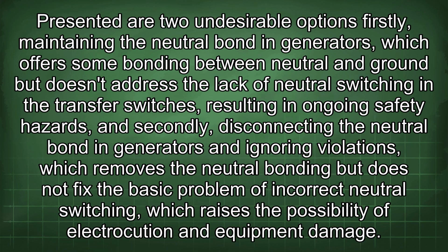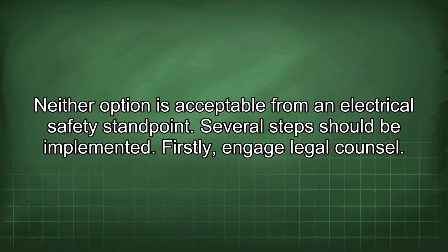Presented are two undesirable options. Firstly, maintaining the neutral bond in generators, which offers some bonding between neutral and ground but doesn't address the lack of neutral switching in transfer switches, resulting in ongoing safety hazards. And secondly, disconnecting the neutral bond in generators and ignoring violations, which removes the neutral bonding but does not fix the basic problem of incorrect neutral switching, which raises the possibility of electrocution and equipment damage. Neither option is acceptable from an electrical safety standpoint.